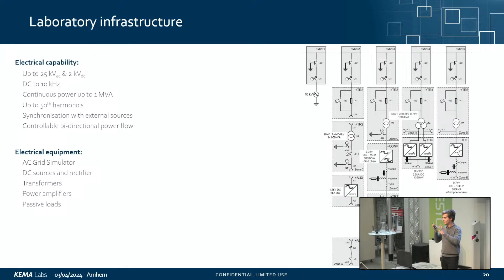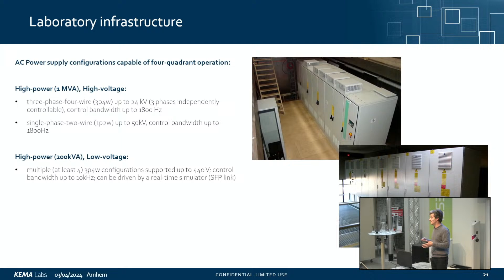What you see there is a very small version of a single line with all the tools and gadgets that we have. On a high level, we have the high voltage, high power AC grid simulator, one of the puzzle pieces to emulate the AC grid you're connected to, giving you the high fidelity that you need on the AC side. Since the opening here, we have also updated our system with low voltage but higher bandwidth amplifiers, which gets us into the next chapter, where you go from 2-3 kilohertz bandwidth amplifiers to 10, 15, 25 kilohertz, adjusting with the requirements and the technology increase from products.